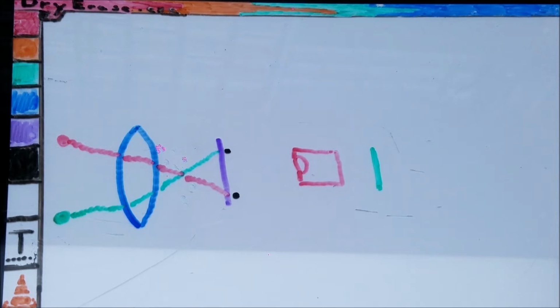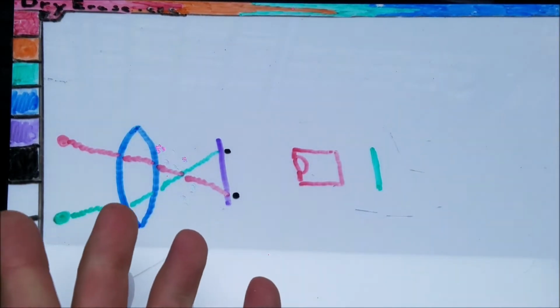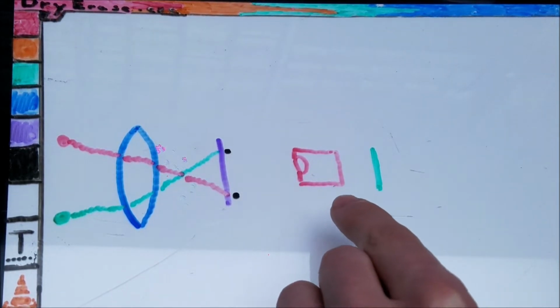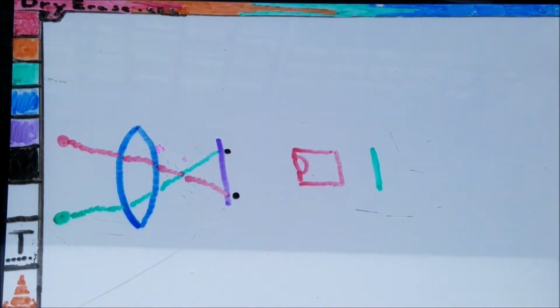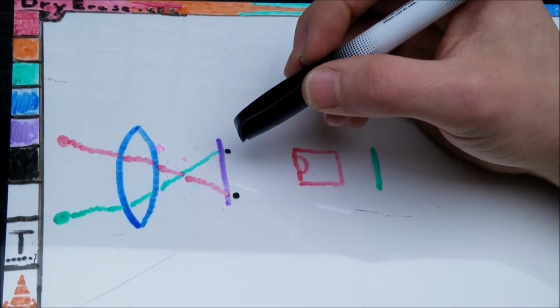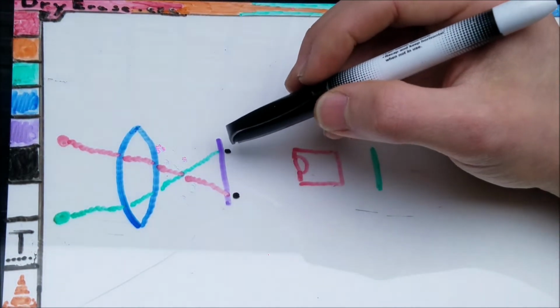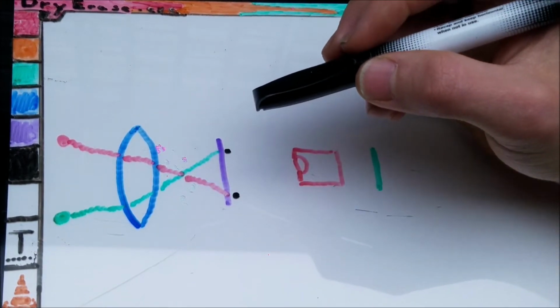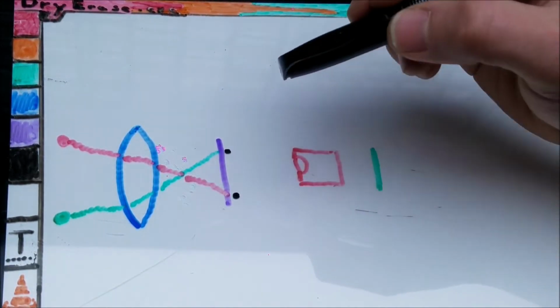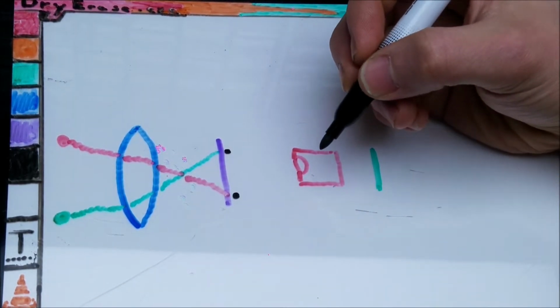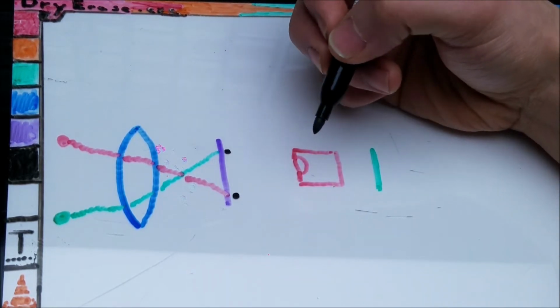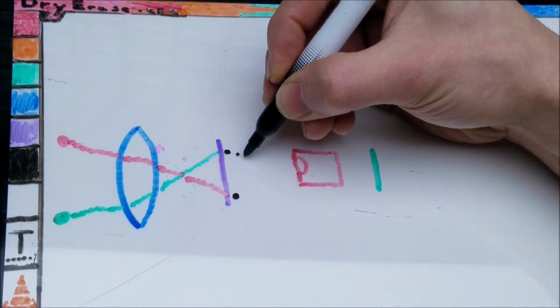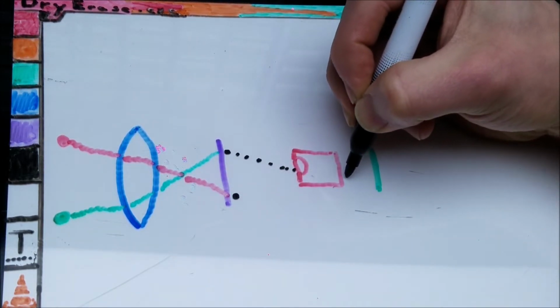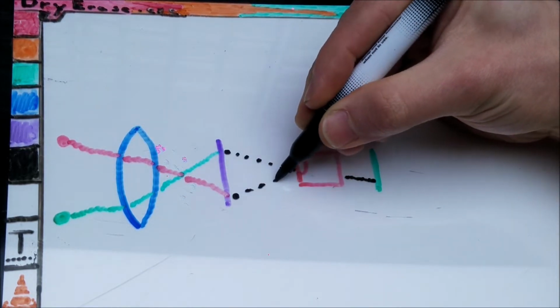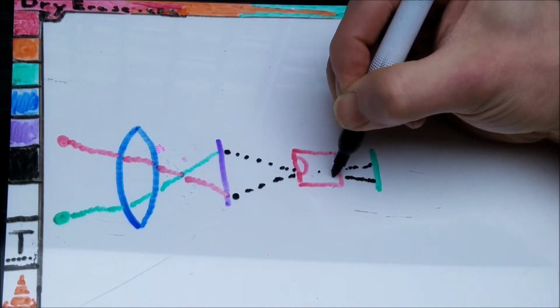Now, what's interesting is that the image is reversed here, but when you look through a night vision tube, you don't see a reversed image. Well, that's because the accelerating anode acts like a lens. It's an electrostatic lens. So let me draw what happens. The amount of electrons produced on the photocathode is determined by the intensity of the photons that hit the photocathode. So the more photons hitting the photocathode, the more electrons are produced. And those electrons are accelerated towards the positive because of their electrical charge, negative, positive, so they attract. So these electrons get pulled in through here, just like this, and kind of come out the other side, like this. It's a very simplistic drawing, but it gets the point across.